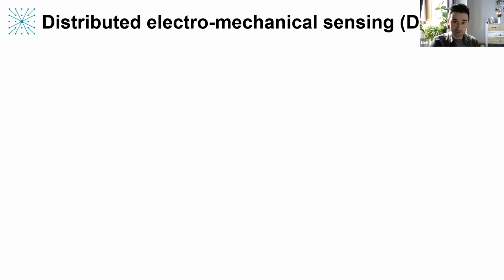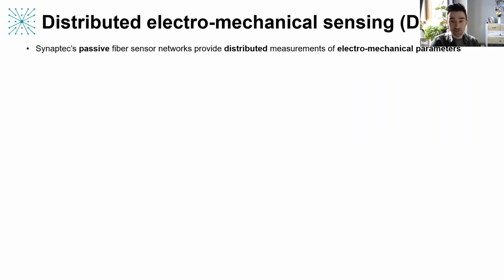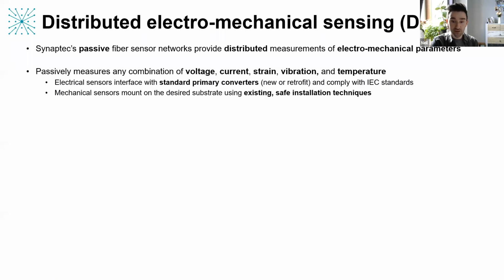So the technology that we have, we refer to as distributed electromechanical sensing, or DES. So what we do is we deploy passive sensor networks leveraging the existing single mode fiber in that network to provide distributed measurement of electrical and mechanical parameters. What this means is if an operator has single mode fibre present in the network, we can splice in passive point sensors for any of these parameters shown here, so voltage, current, strain, vibration, and temperature.